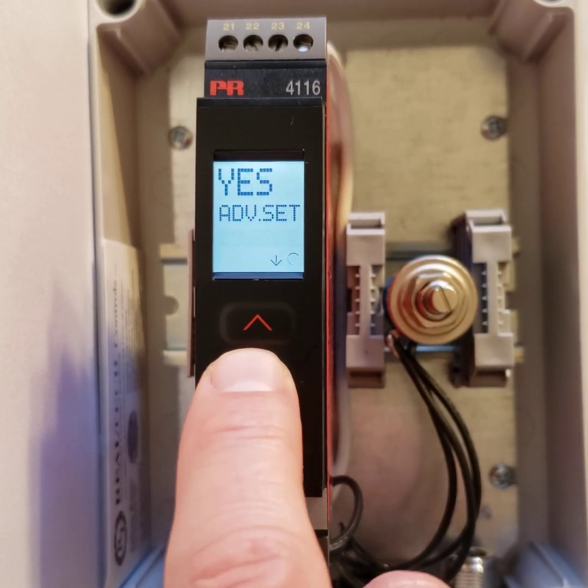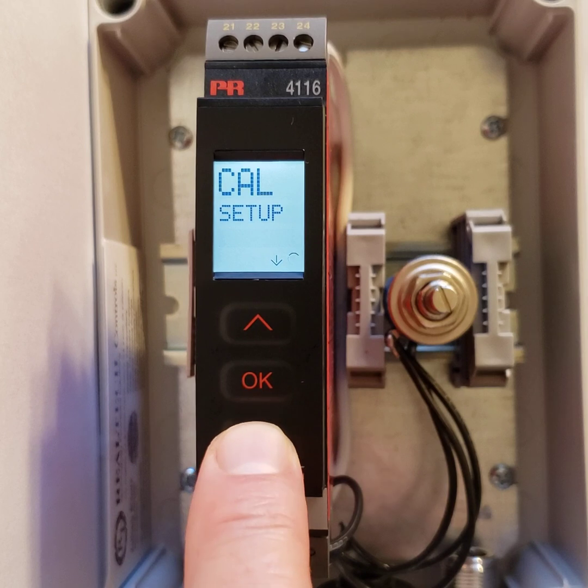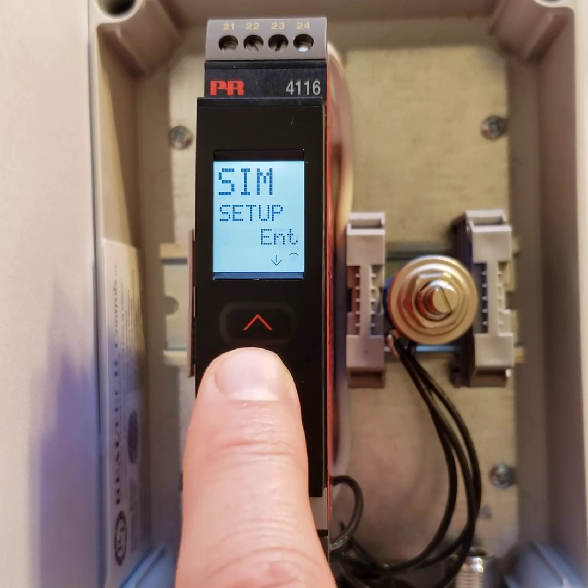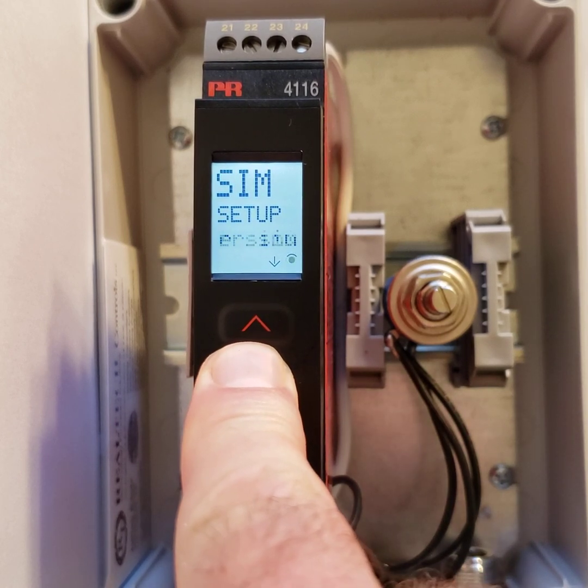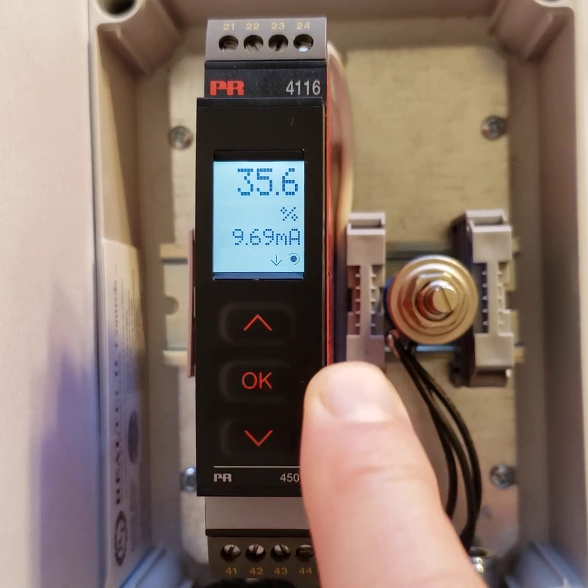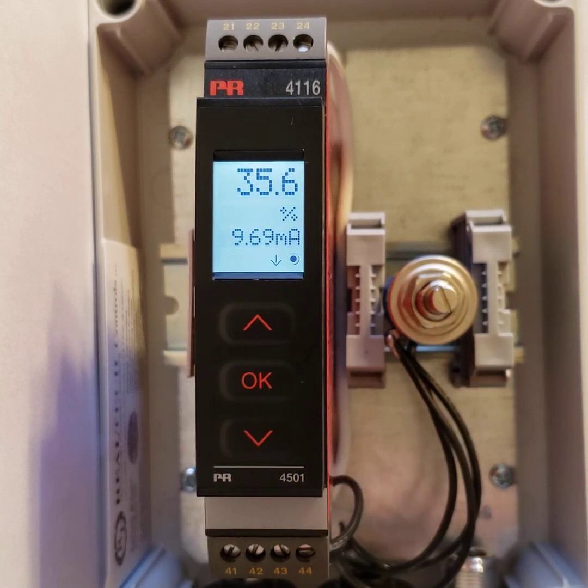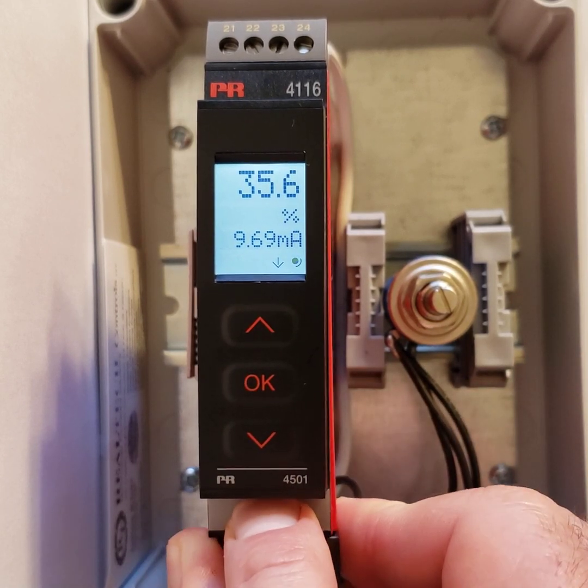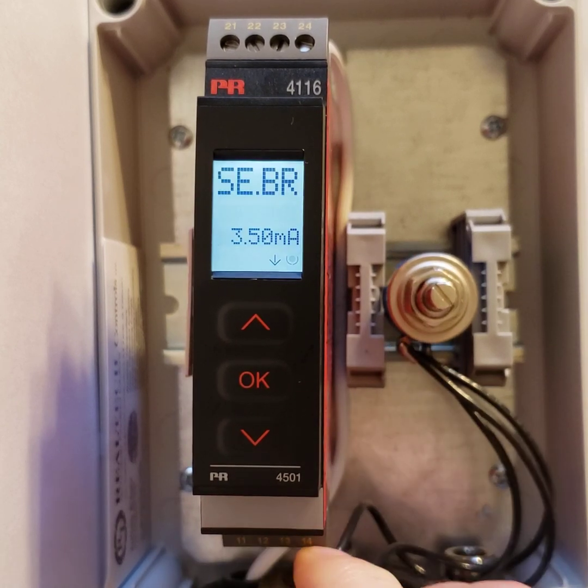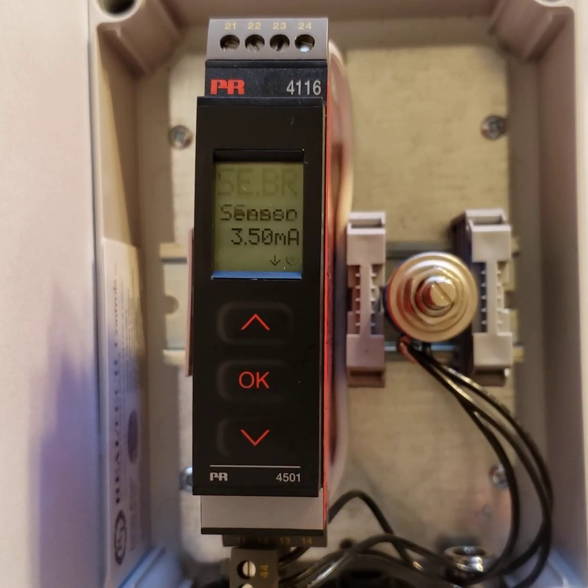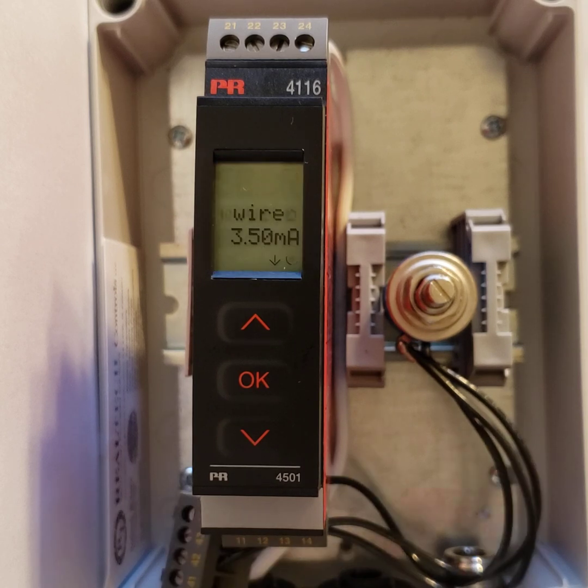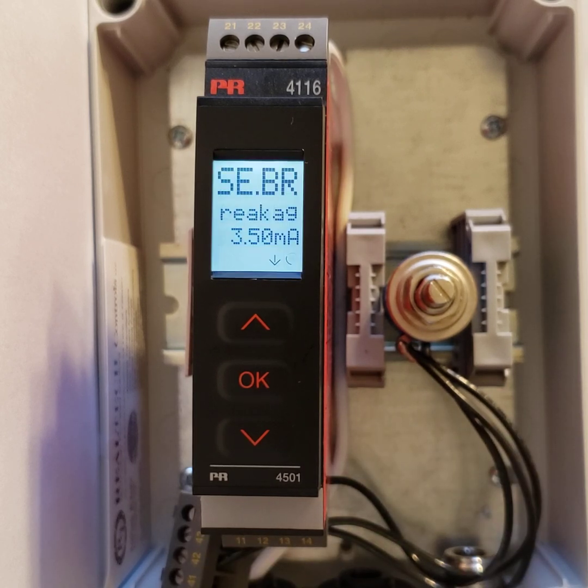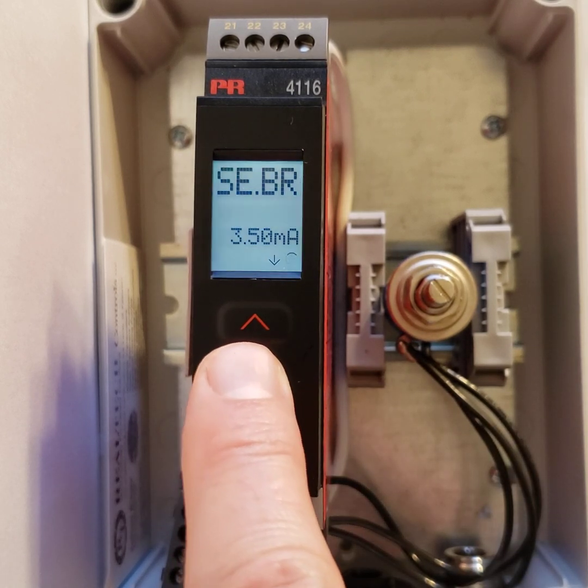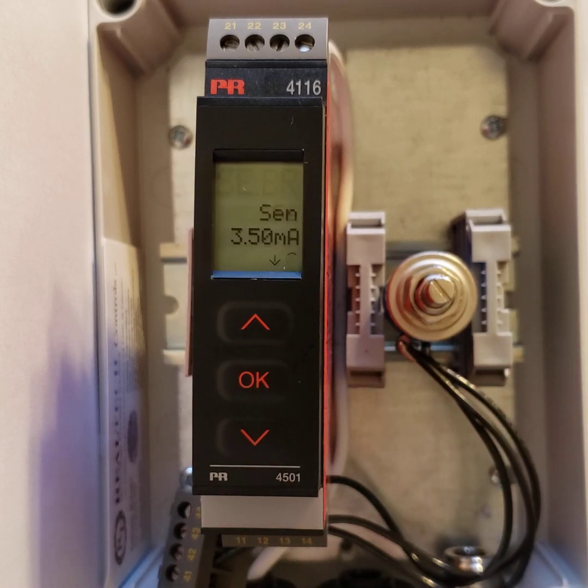The next item in the menu is simulate. So say I'm just going to hold the OK button and that gets me out of the menu. If you hold the OK, it scrolls backwards. Say I have a signal break. I'm going to just take the input away. And now it gives me a sensor break with 3.5 milliamps because I've programmed it to go low on a sensor break. But now I can't have this process shut down.